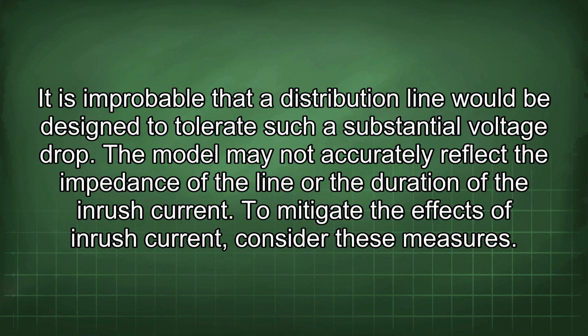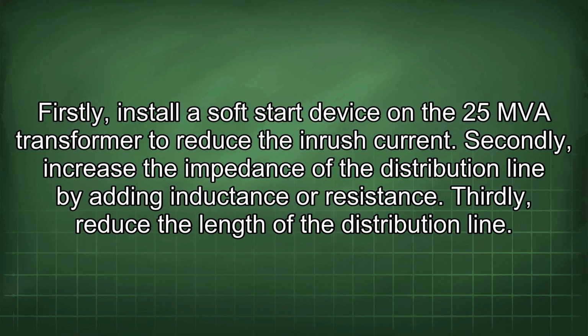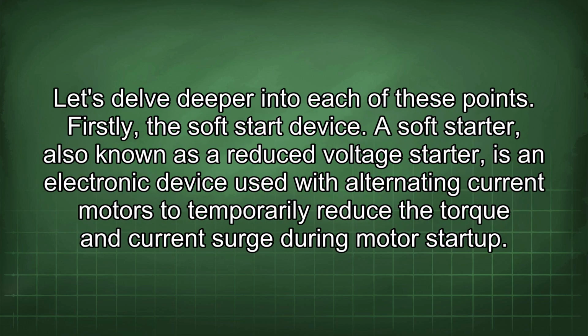To mitigate the effects of inrush current, consider these measures. Firstly, install a soft start device on the 25 MVA transformer to reduce the inrush current. Secondly, increase the impedance of the distribution line by adding inductance or resistance. Thirdly, reduce the length of the distribution line. Let's delve deeper into each of these points. Firstly, the soft start device.